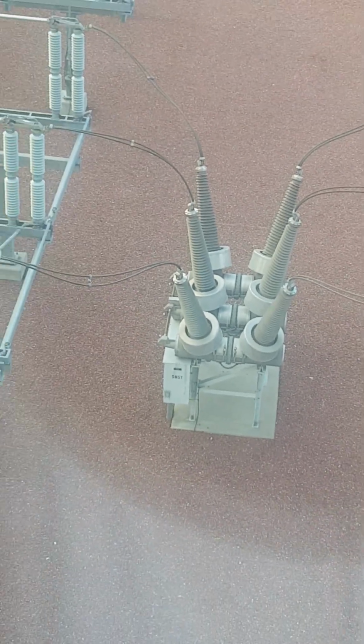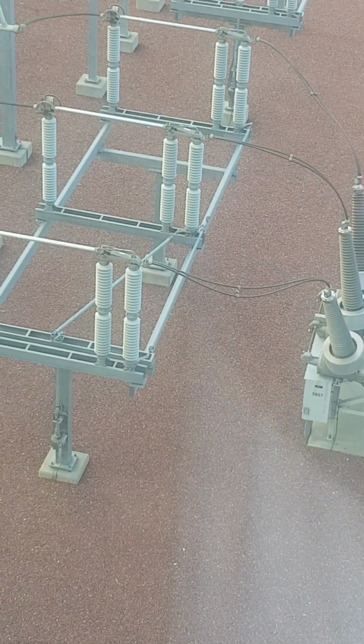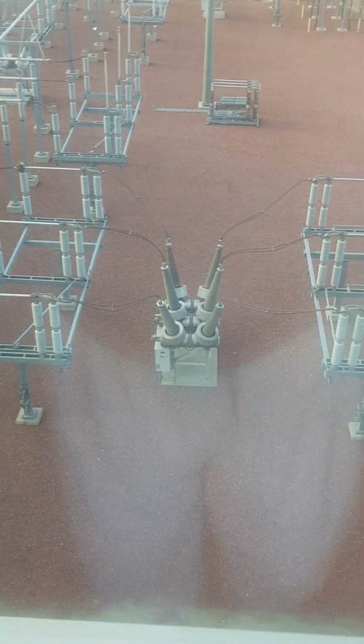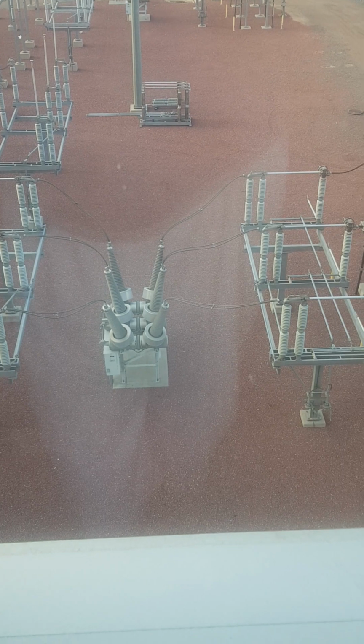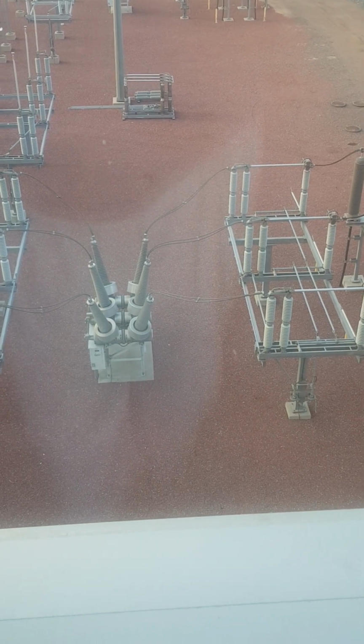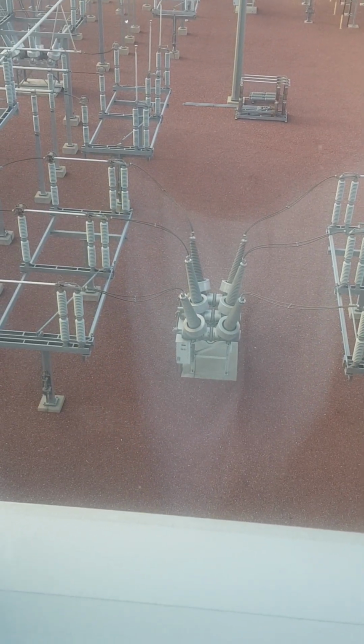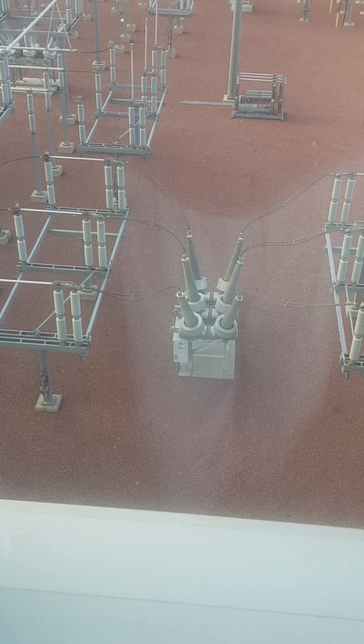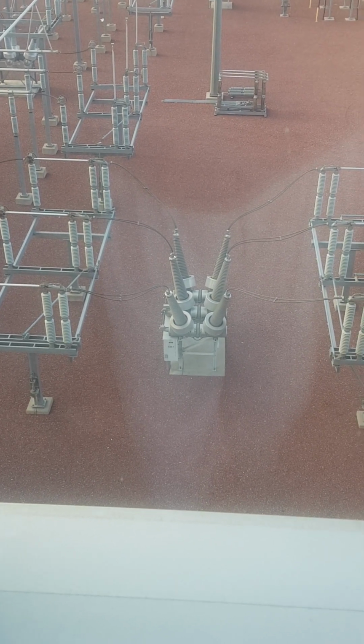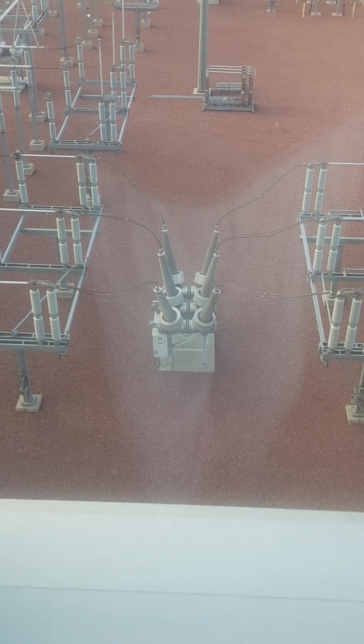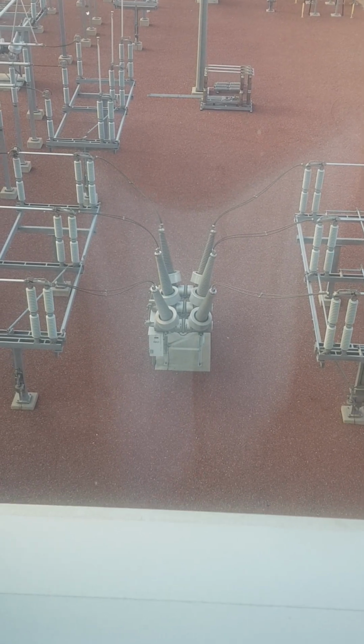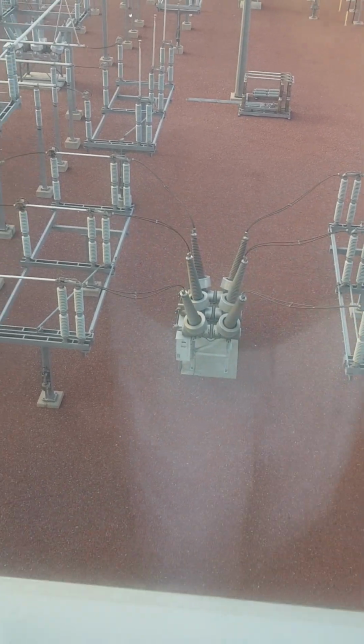And then here we have another disconnector. So basically here you see two disconnectors, one at the beginning of the breaker and one at the end. And this is very, very common. You open it from both sides to completely disconnect the breaker from any power so that we can do some maintenance on it.